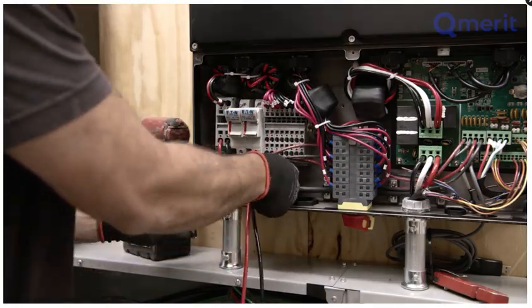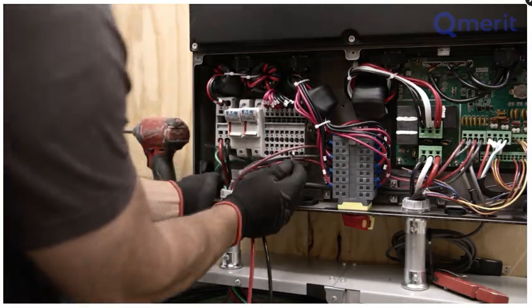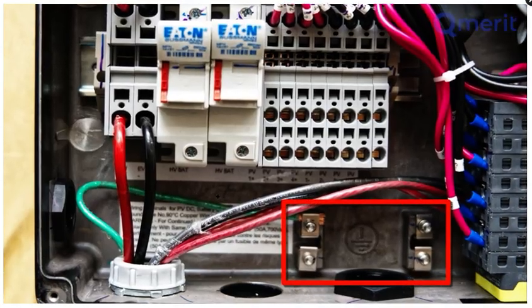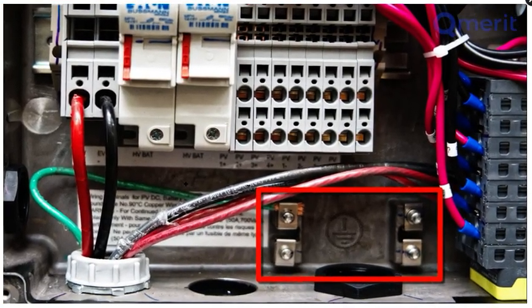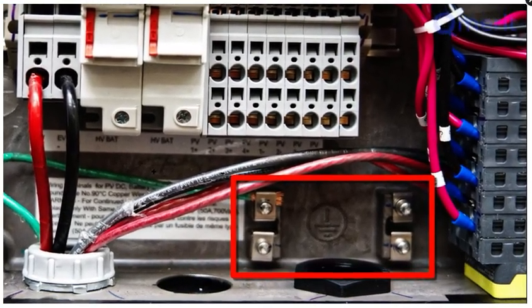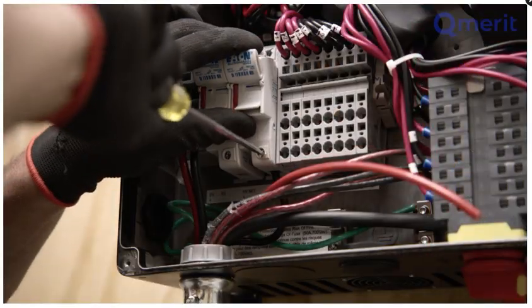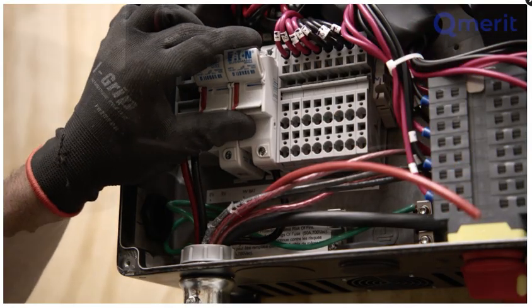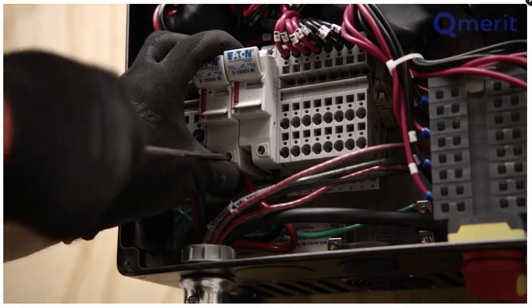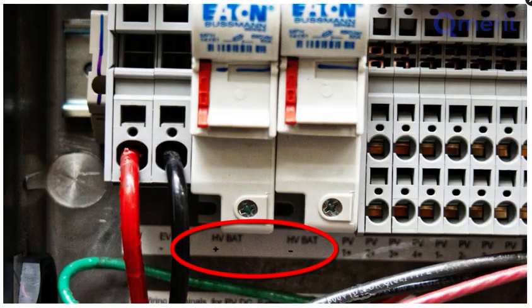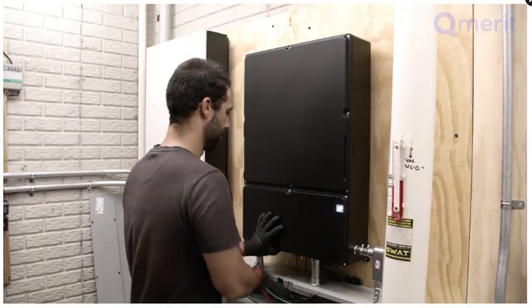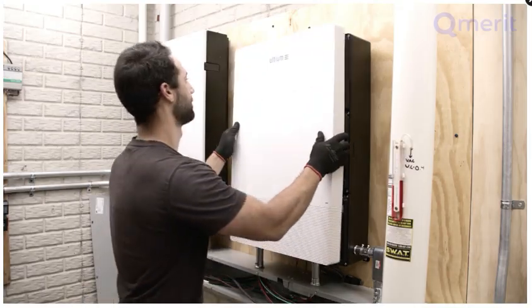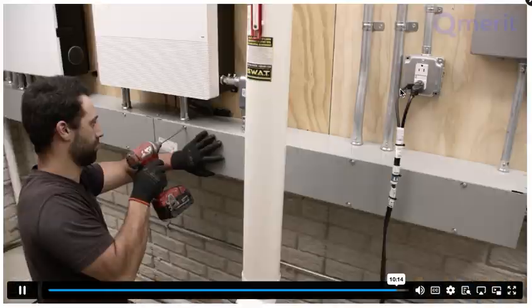We now wire the high voltage wires. Starting with the ground wire, there are 4 grounding screws within this inverter. You can land up to 2 ground wires per screw. There is a pre-installed Eaton breaker that will receive the positive and negative wires from the BCU. Designated markings underneath the breaker show that the right side of the breaker receives the negative input and the left side receives the positive input wire. This installation is complete. It's time to put the covers back on.